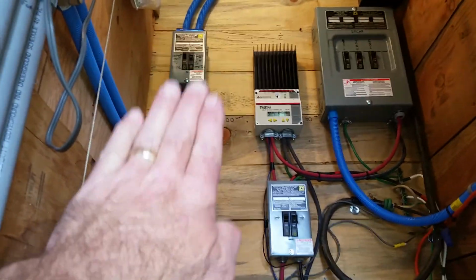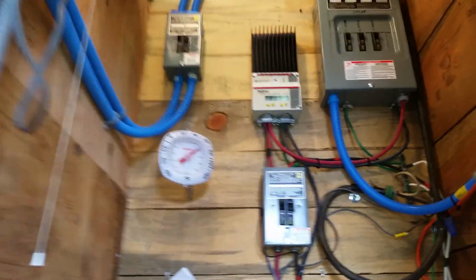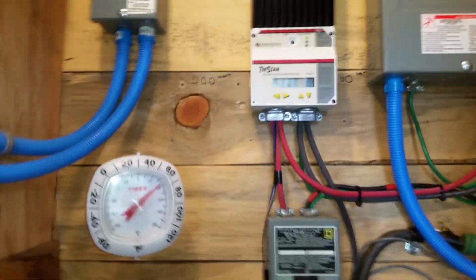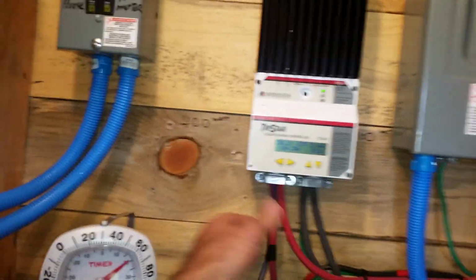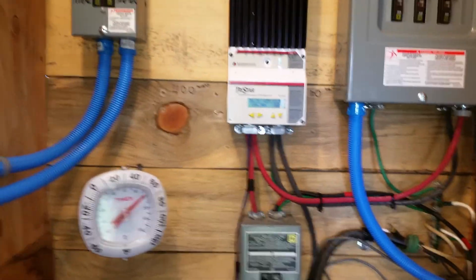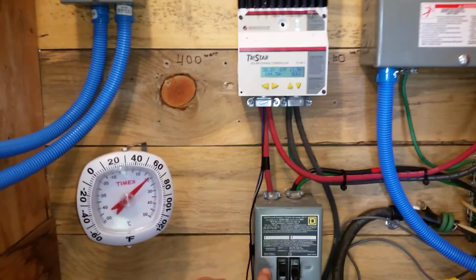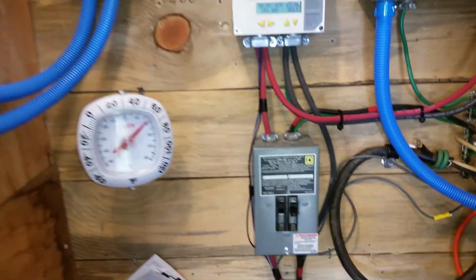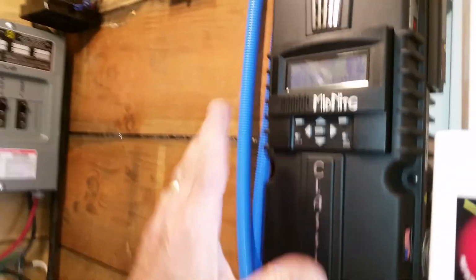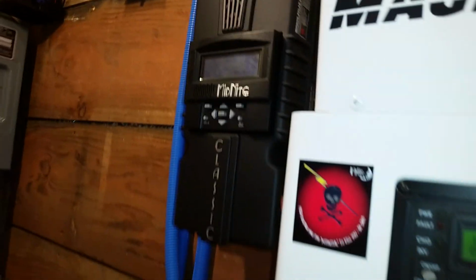Right now I'm showing you the one system that is not in conduit, but it's the lower voltage system, so the shock potential is down, but its fire potential is still very high. That's why it's fused correctly, both coming in and going out. Everything involved with the higher voltage stuff is all in conduit, all to code, and I'll show you why.